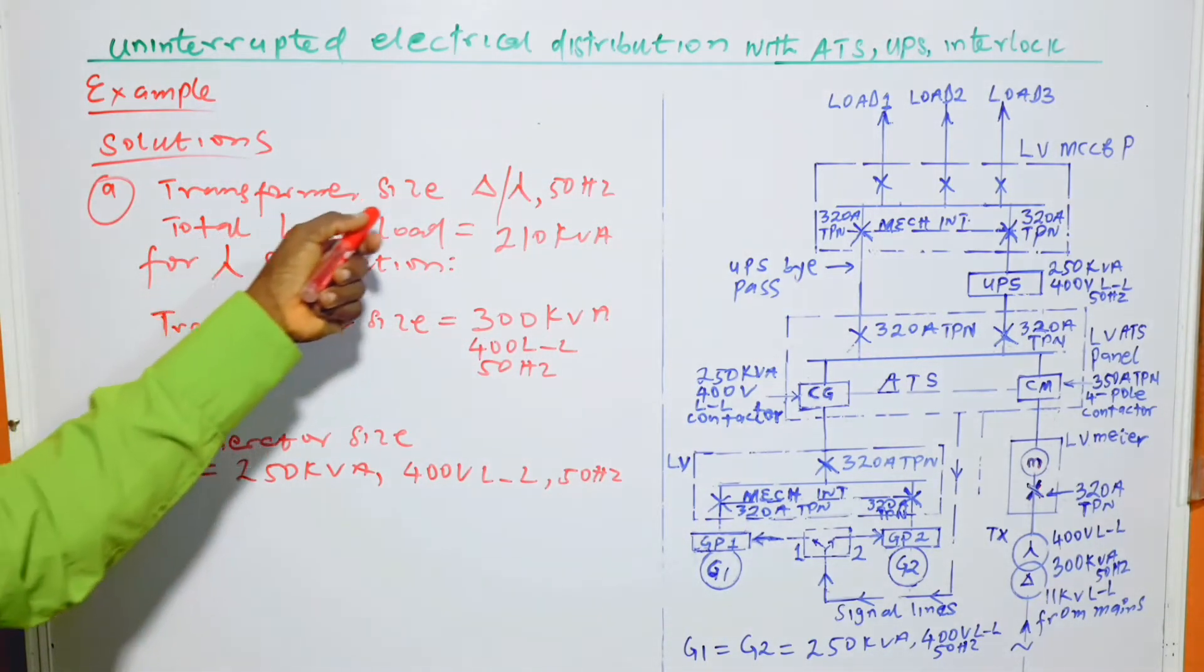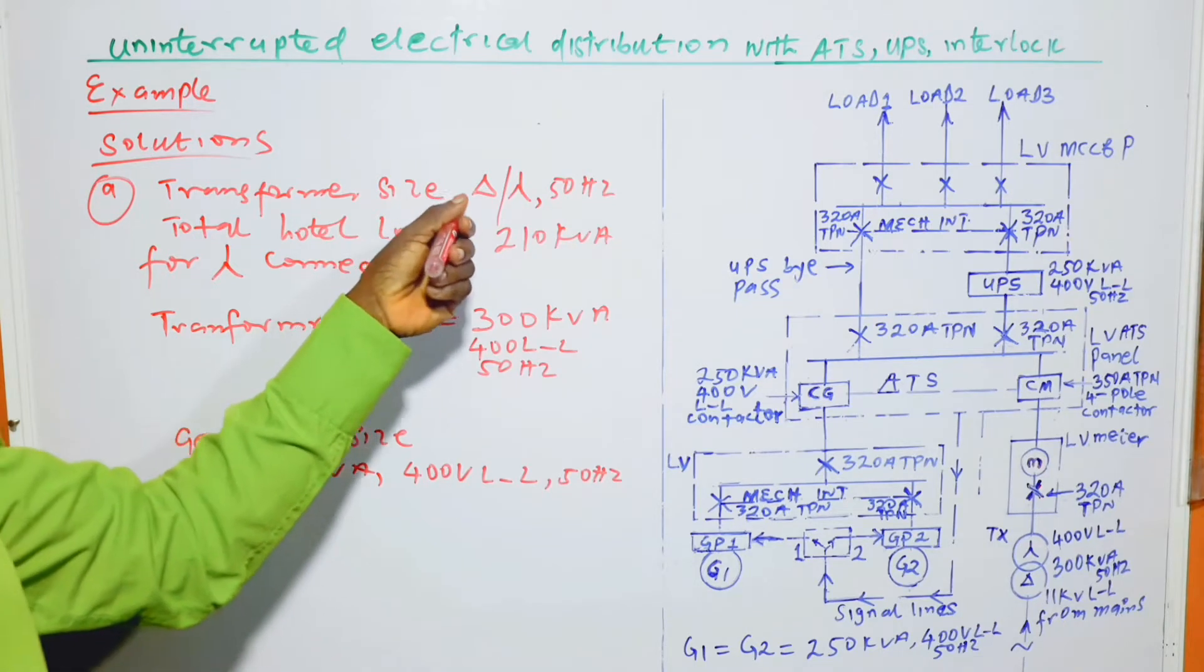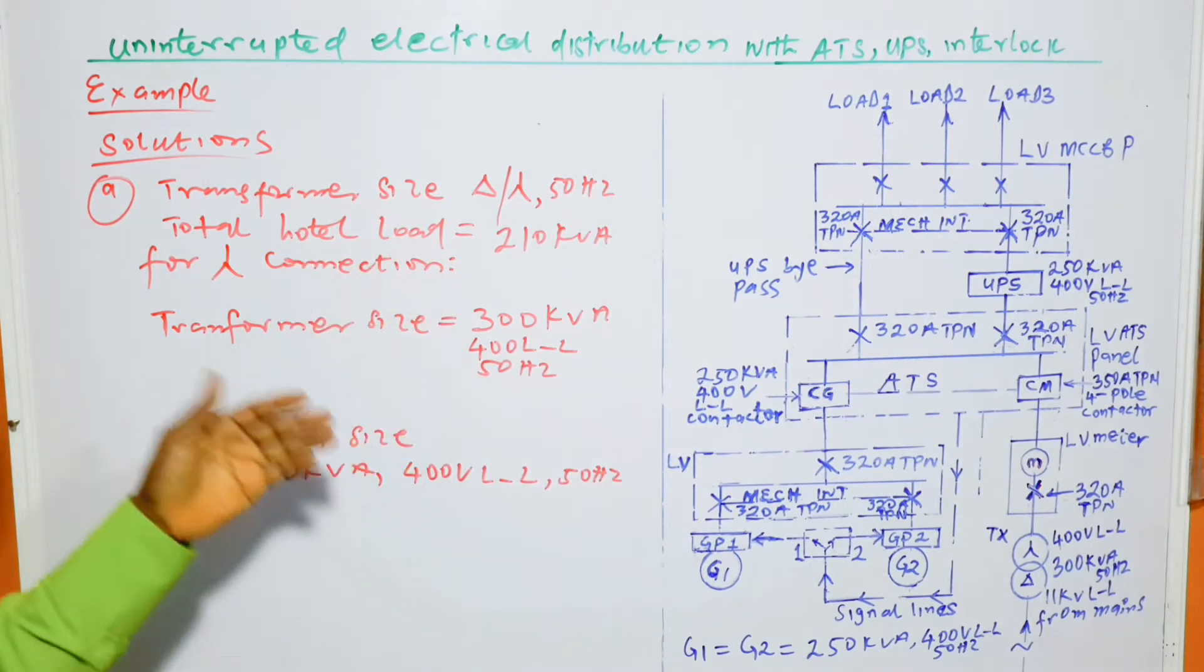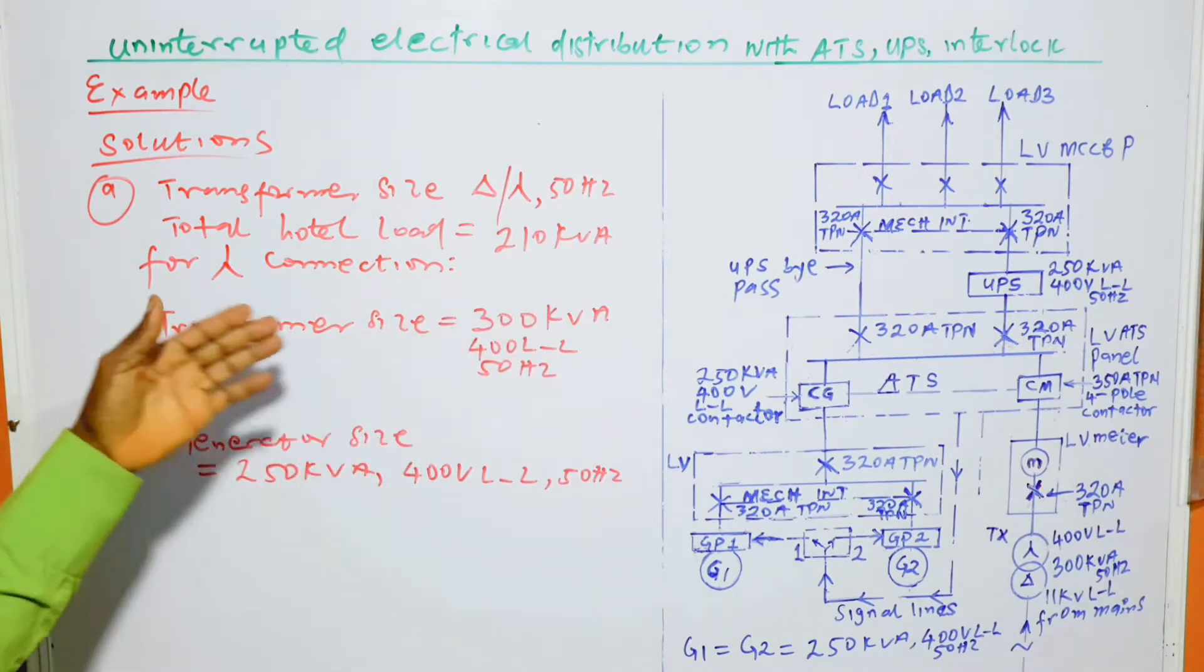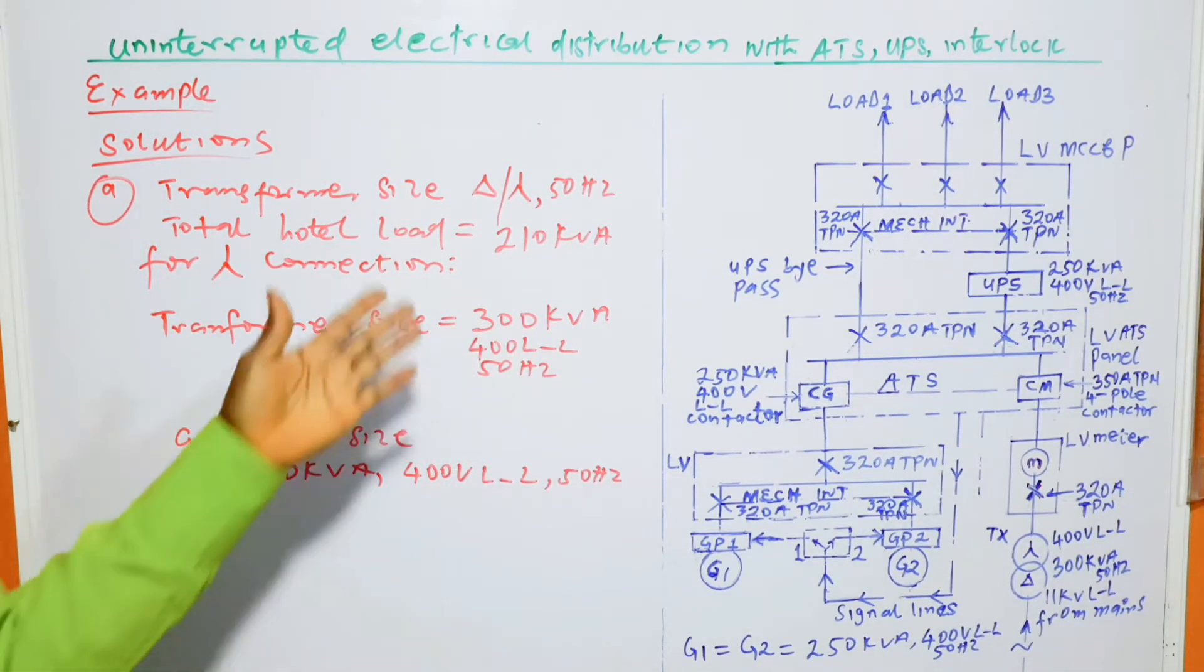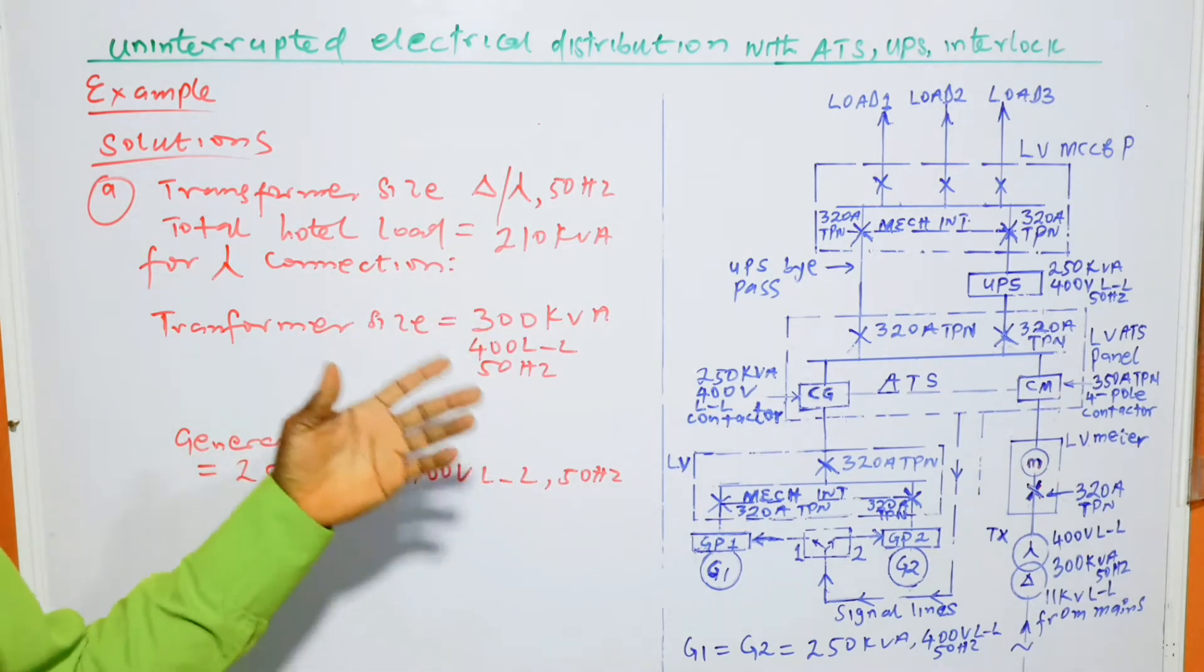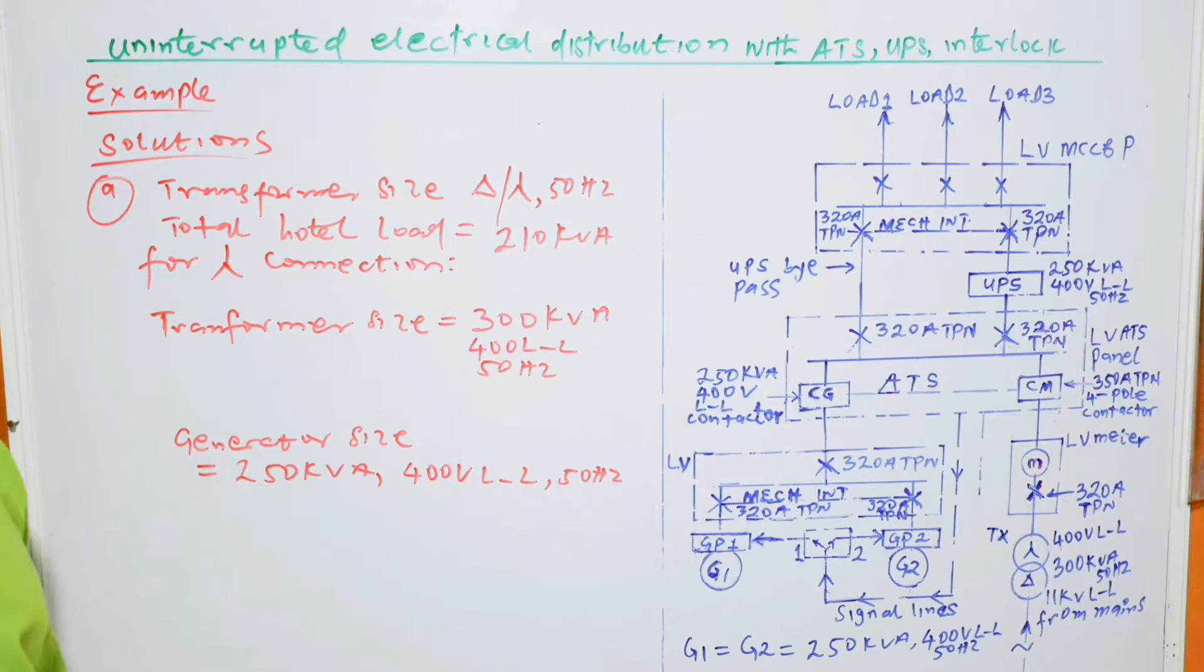Solving the problems. In part A, the transformer size, as given by the question, the transformer is delta star at 50Hz frequency. So the total hotel load is 210kVA. So the transformer size is 300kVA. 300kVA is higher than 210kVA and it also takes care of the future incremental load.